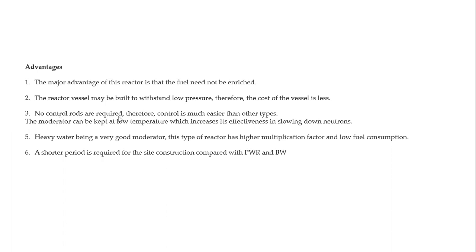No control rods are required, therefore control is much easier. Heavy water is a very good moderator. These types of reactors have higher multiplication factors and low fuel consumption. A shorter period is required for site construction compared to the PWR and BWR. These are some of the advantages of CANDU type reactors.